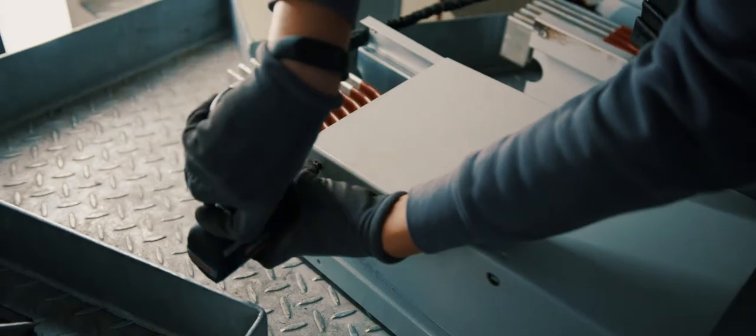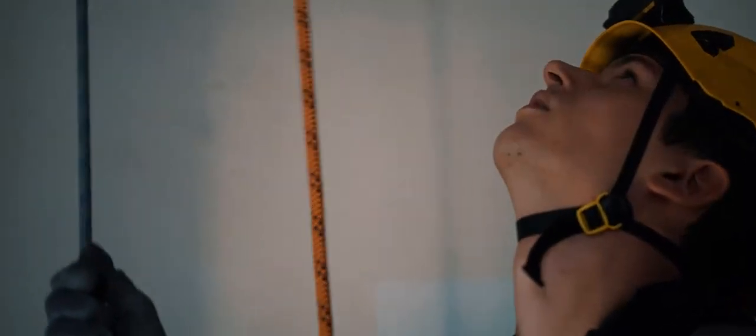We descend on the cord to start the dismantling of the bus bar. We have an electric panel which allows us to hold the bus bar and we replace it with a new one. This can seem simple, but on a piece of 100 kg and 3.50 metres, on the cord, it's not simple. It's an impressive operation.